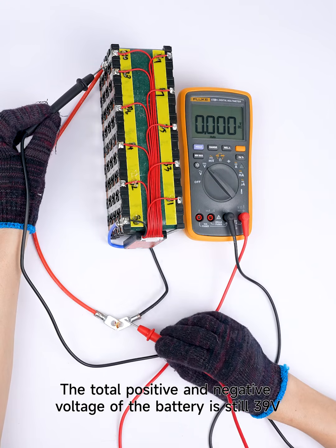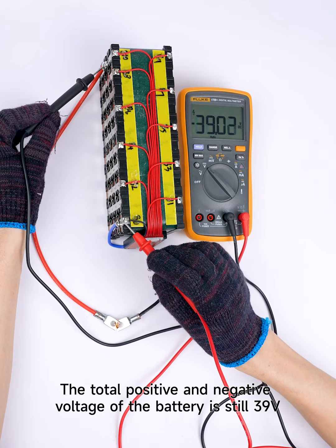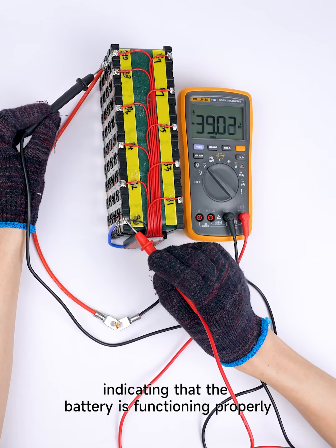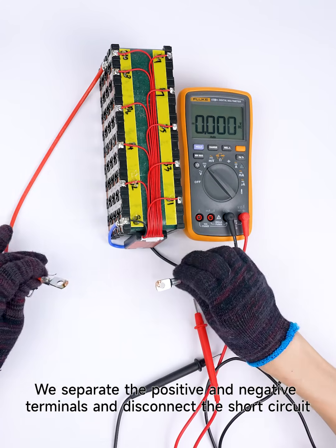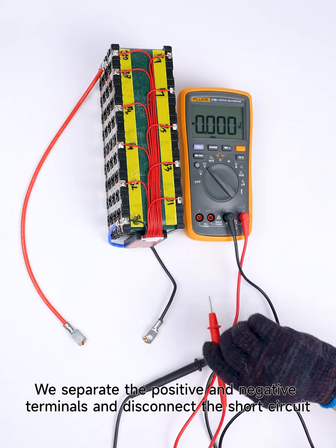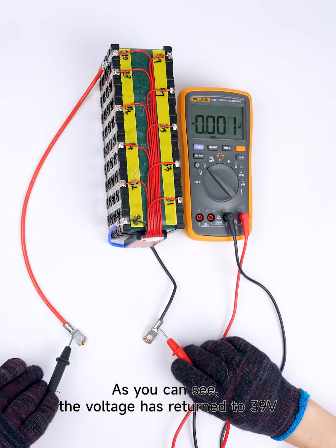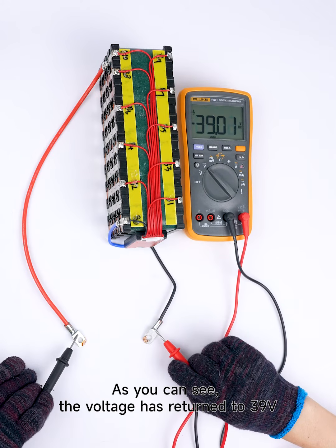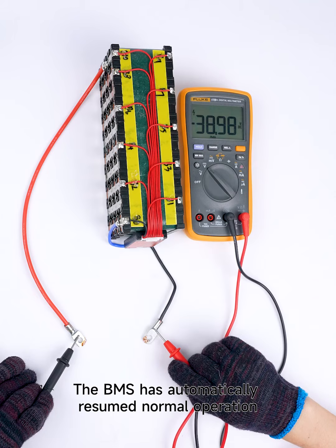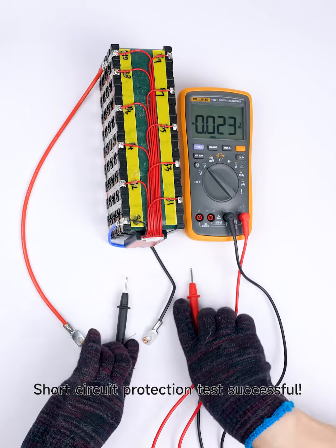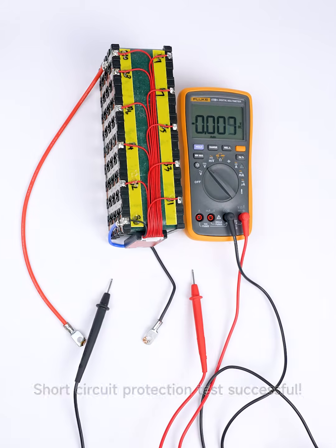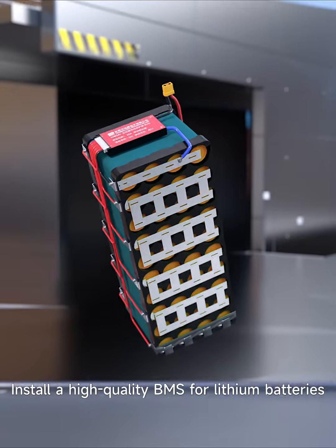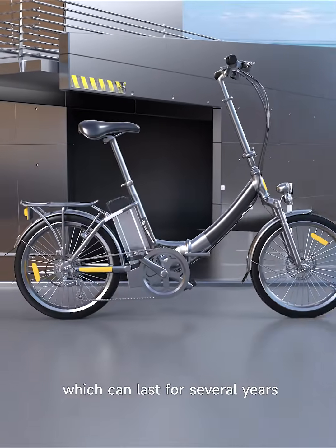The total positive and negative voltage of the battery is still 39 volts, indicating that the battery is functioning properly. We separate the positive and negative terminals and disconnect the short circuit. As you can see, the voltage has returned to 39 volts. The BMS has automatically resumed normal operation. Short circuit protection test successful. Install a high-quality BMS for lithium batteries, which can last for several years.